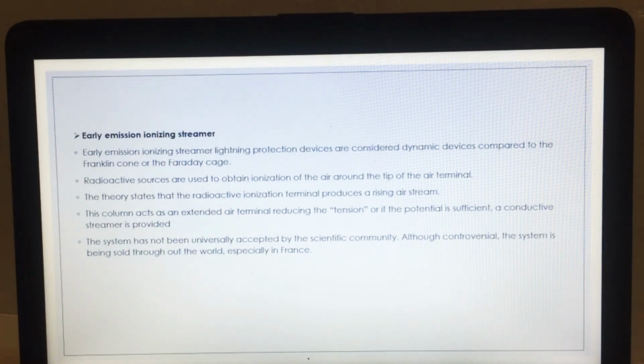Early emission ionizing streamer lightning protection devices are considered dynamic devices compared to the Franklin cone or the Faraday cage. Radioactive sources are used to obtain ionization of the air around the tip of the air terminal. The theory states that the radioactive ionization terminal produces a rising air stream. This column acts as an extended air terminal, reducing the tension, or if the potential is sufficient, a conductive streamer is provided. The system has not been universally accepted by the scientific community.